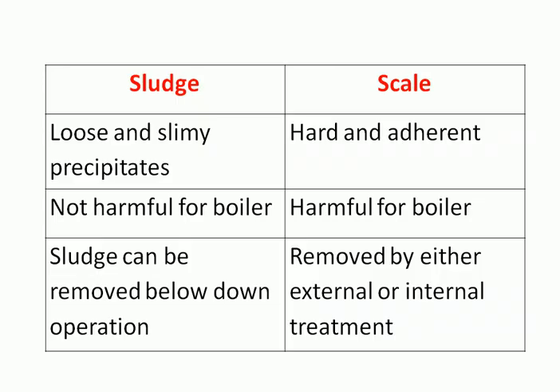What is the difference between sludge and scale? Sludge is loosely and slimly precipitated, while scale is a hard adherent coating on the inner walls of the boiler. Sludge is not harmful to the boiler, but scale is harmful due to its effect on heat transfer. Sludge can be removed by the blow down operation, while scales are removed by either external or internal treatment of the boiler.